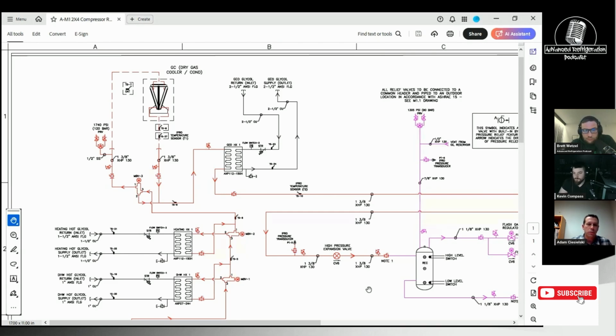And just one correction, we'll never take direct hot gas into the coils. The supply side will utilize basically a hot gas or defrost regulator. Mm-hmm. And that can open and close. It's typically a stepper valve that opens and closes. So not only can we control the pressure, we can control the rate of change. When we go into defrost, we might open that up very slowly and let the pressure build slowly over time, not to shock the coil. Mm-hmm. And then on the return side, we have what we would call a discrete regulator. And that in itself gives us the capability to raise or drop that defrost temperature, which is always going to be above the receiver because you need a pressure differential to move it. Mm-hmm. But having those two valves gives us the freedom to make a lot of adjustments to fine tune the defrost time and cycle.